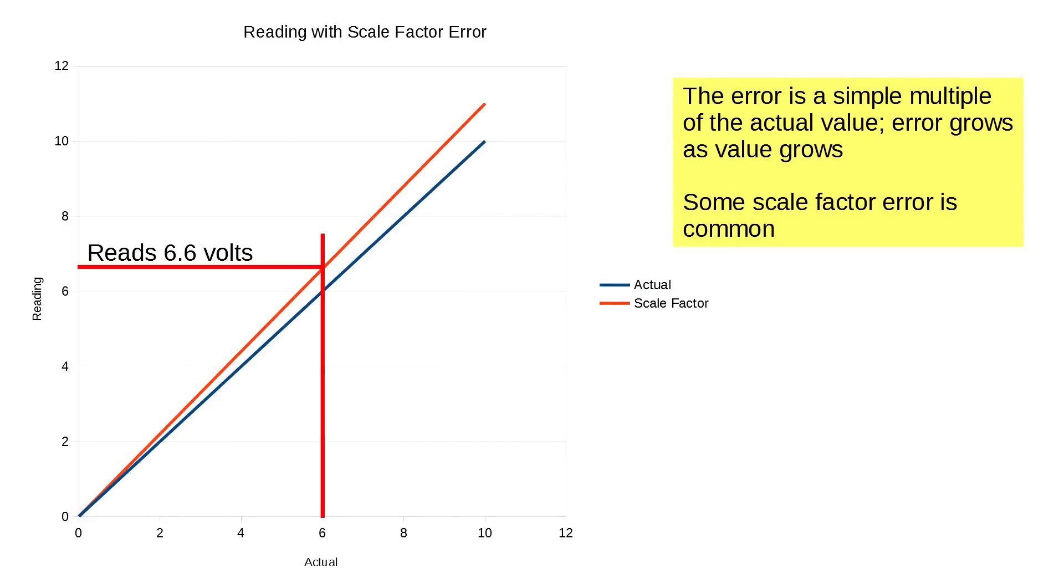Here's a scale factor error. Notice the shape of the curve is a little different. You get down toward the bottom where the zeros are, and there is no error. But the error is a multiple of the actual value. It grows as the actual value grows. Some scale factor error is common in instruments, not to this degree. I mean, this is a 10% scale factor error. So, an actual six-volt reading gives us a readout of 6.6 volts.